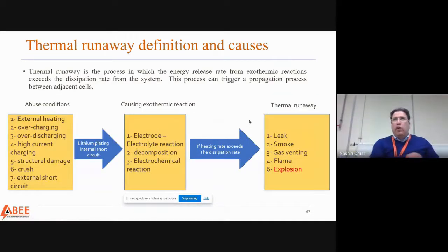Now, what could contribute to abuse conditions? As I mentioned, that could be external heating where temperature gets very high, or overcharging. Typically batteries with NMC have a maximum voltage around 4.3 volts, LFP around 3.8 volts. If you go over that condition, some elements become unstable. Over-discharge, extremely high current charging rates, structural damage, or external short circuits are typical problems that happen.